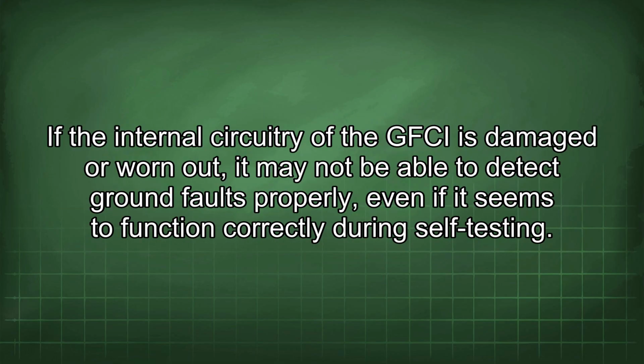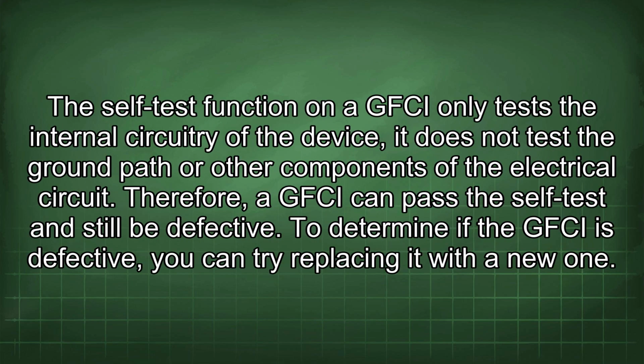If the internal circuitry of the GFCI is damaged or worn out, it may not be able to detect ground faults properly, even if it seems to function correctly during self-testing. The self-test function on a GFCI only tests the internal circuitry of the device. It does not test the ground path or other components of the electrical circuit. Therefore, a GFCI can pass the self-test and still be defective.